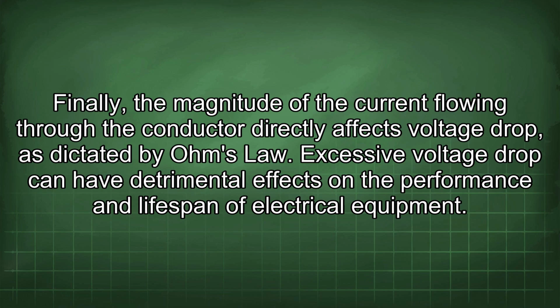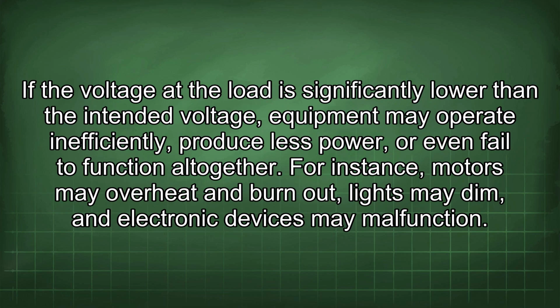Excessive voltage drop can have detrimental effects on the performance and lifespan of electrical equipment. If the voltage at the load is significantly lower than the intended voltage, equipment may operate inefficiently, produce less power, or even fail to function altogether. For instance, motors may overheat and burn out, lights may dim, and electronic devices may malfunction.